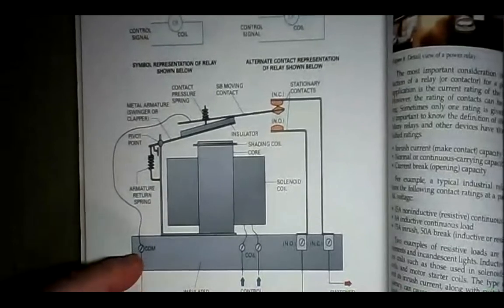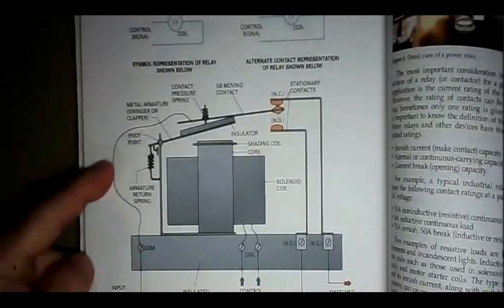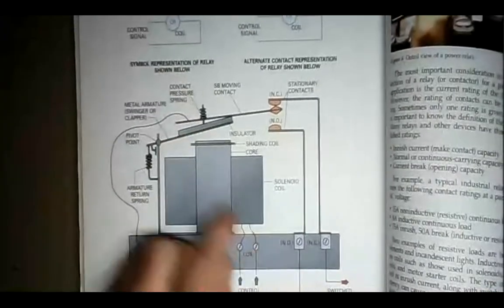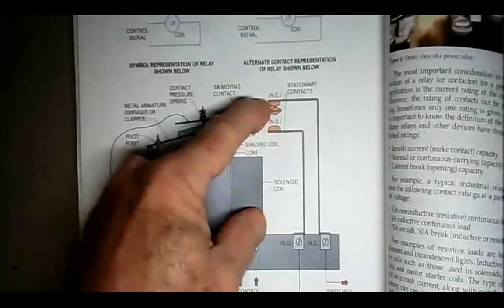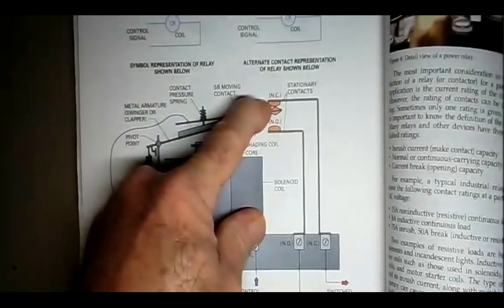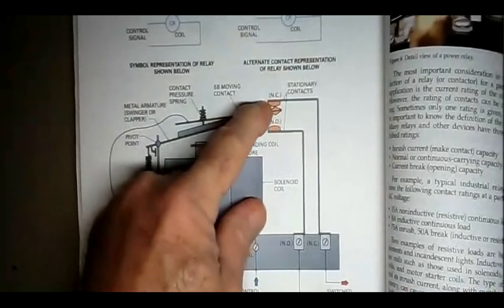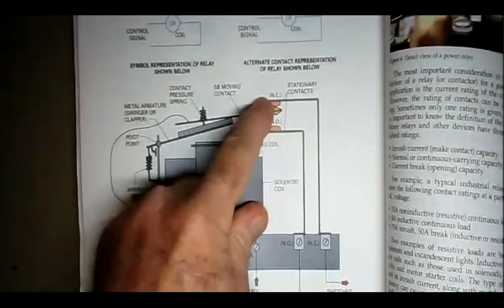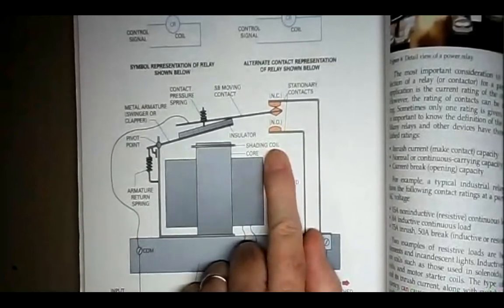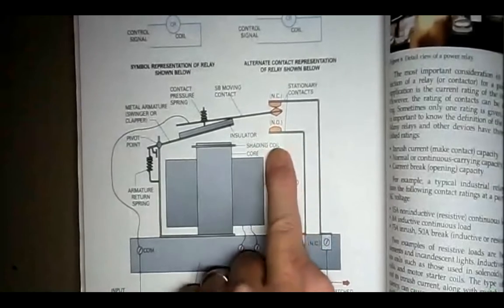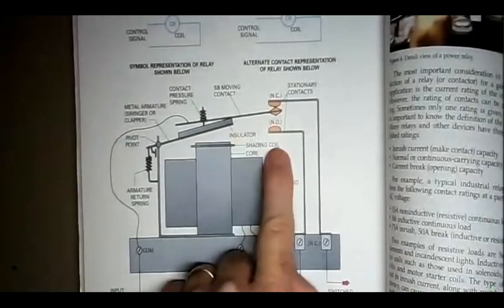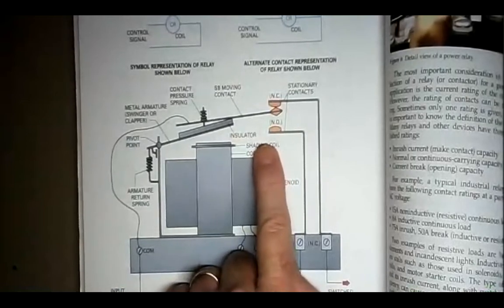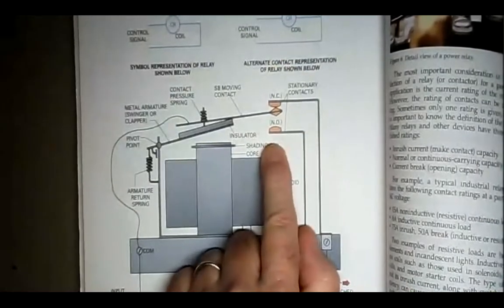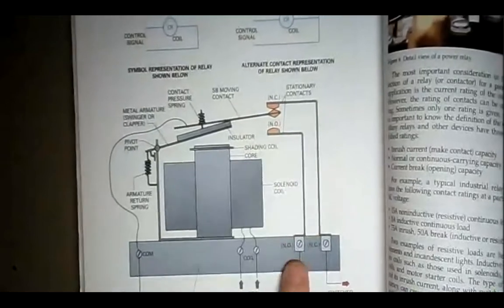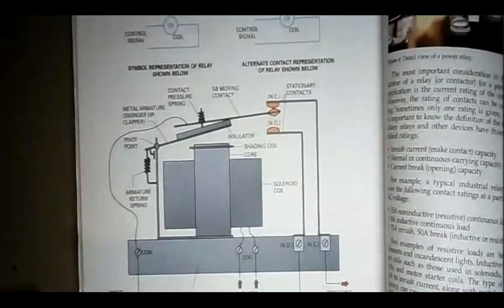Here's your common. The common is going up to this contact bar, and the contact bar can be in one of 2 positions. There's a normally closed, which means off the shelf, out of the box, in your hand, this contact is closed. It's normally closed. Off the shelf, out of the box, in your hand, this contact is normally open with respect to the common. So it's designated as normally open. When you energize, this contact bar moves, and the normally open contact closes, and the normally closed contact opens. So normally open, normally closed, and the common provides the power.